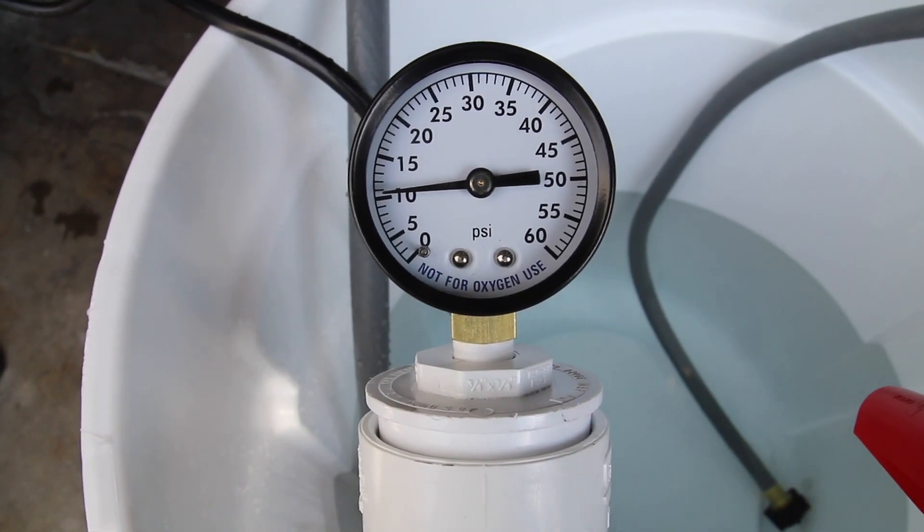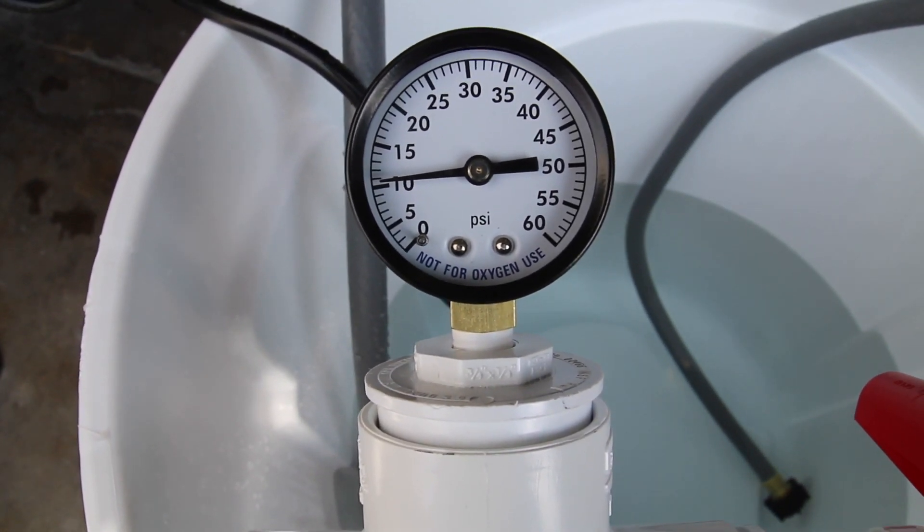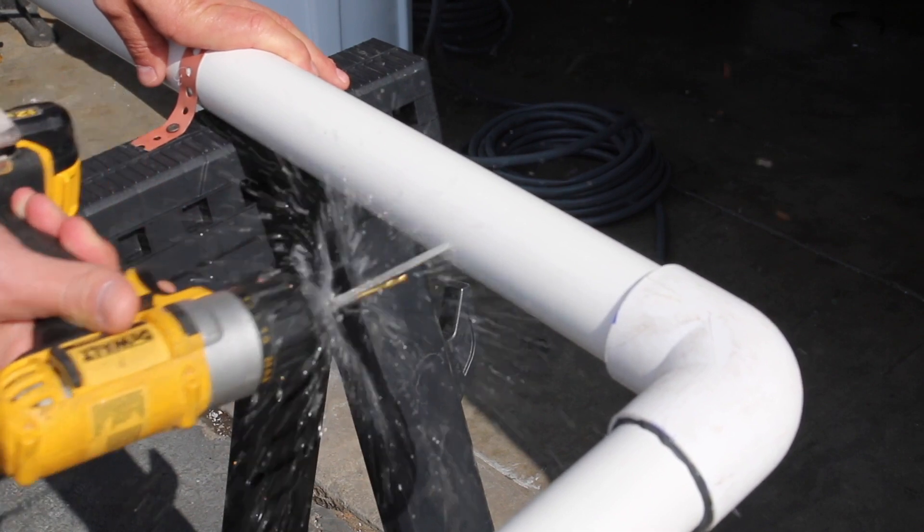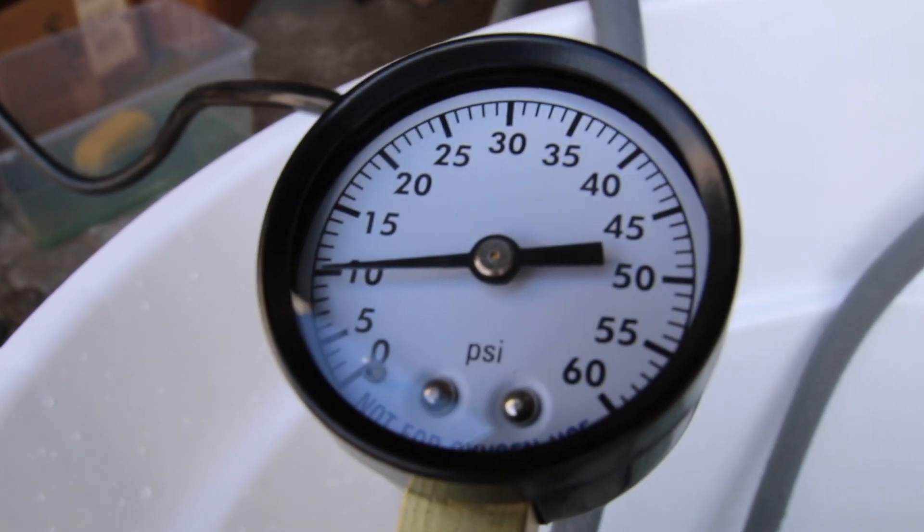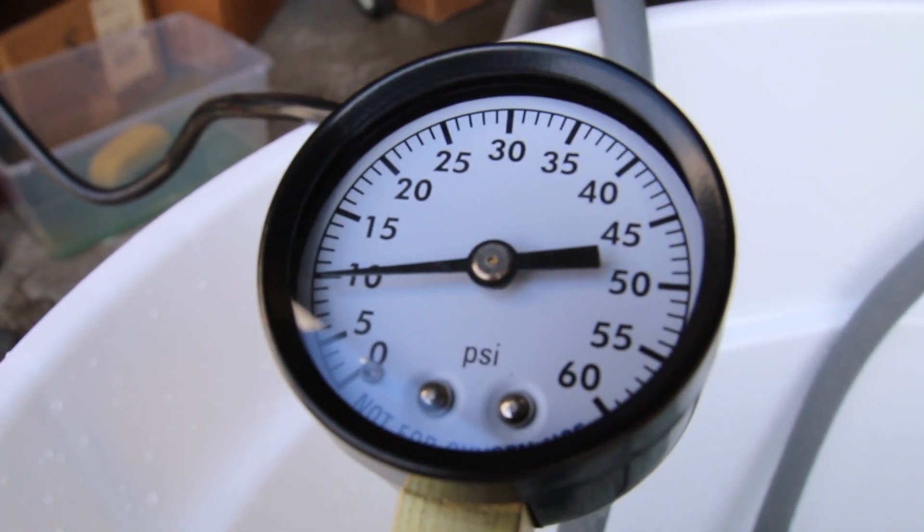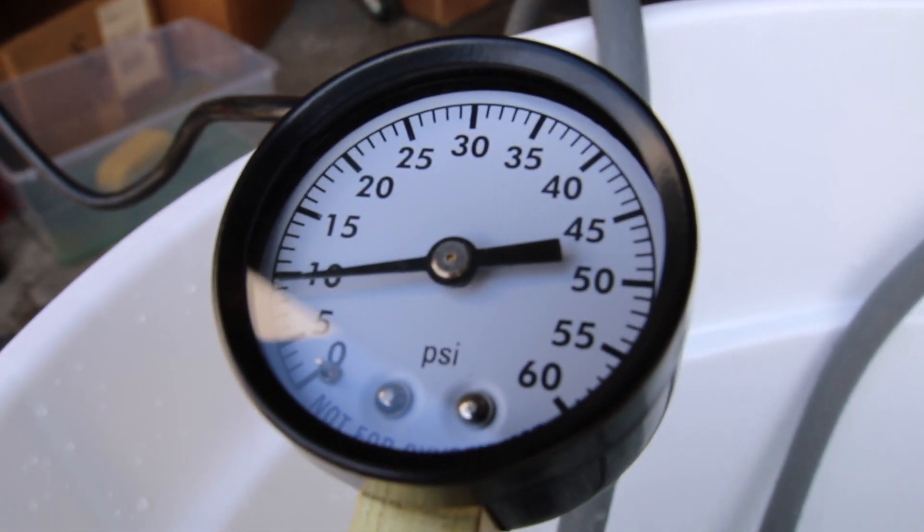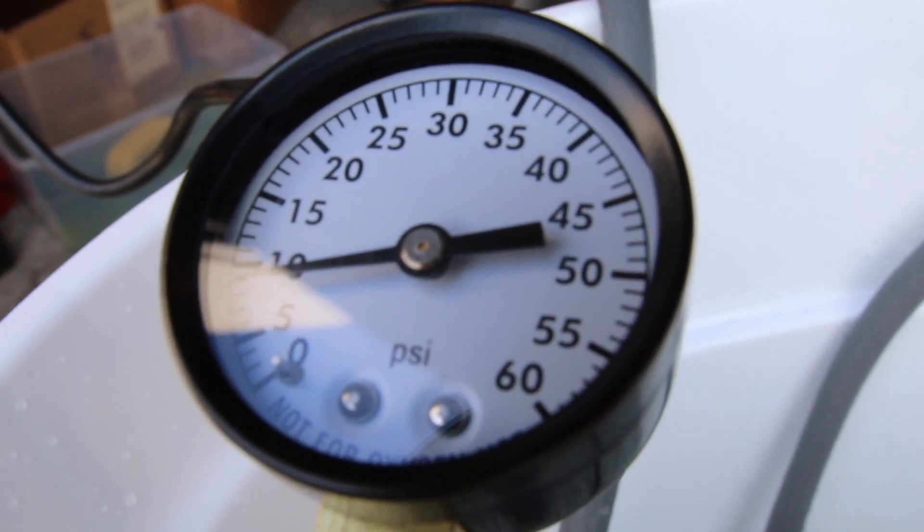What we're showing you here is the pipe is not leaking right now. It's set at about 11 pounds, and now we're going to create the leak. We drilled with a 1/8 inch hole, and now you can see the pressure drop. That's because the leak is happening.